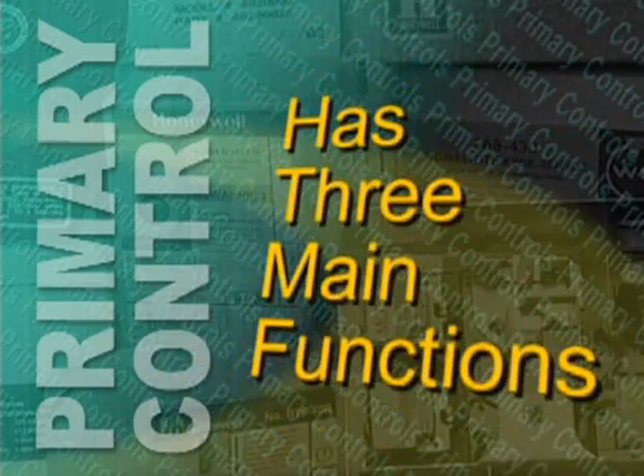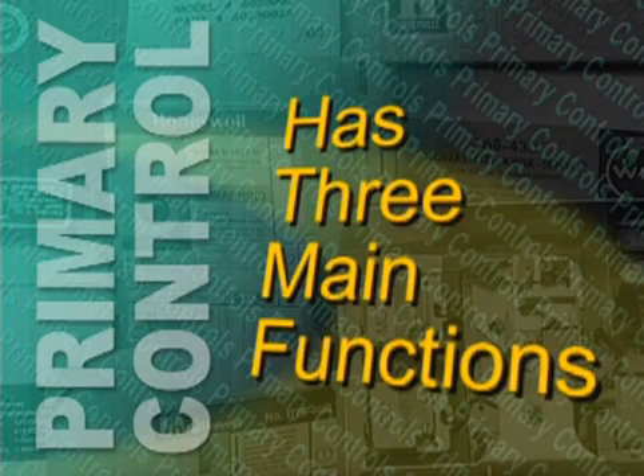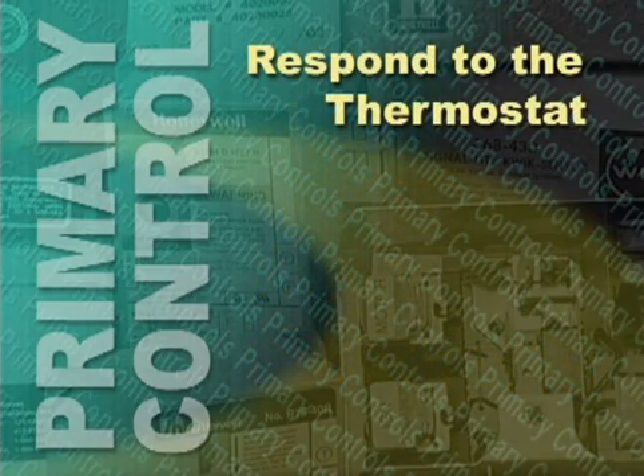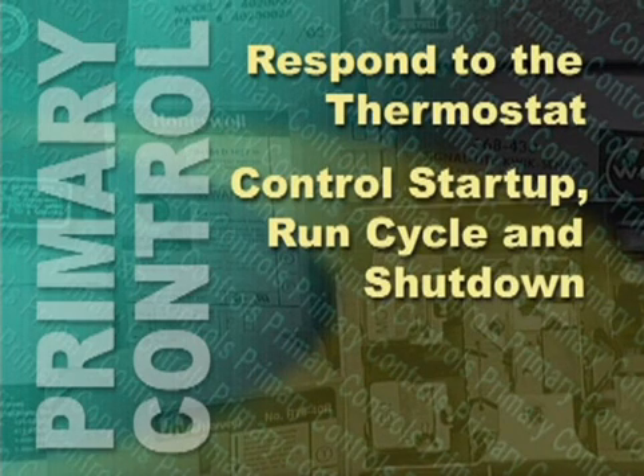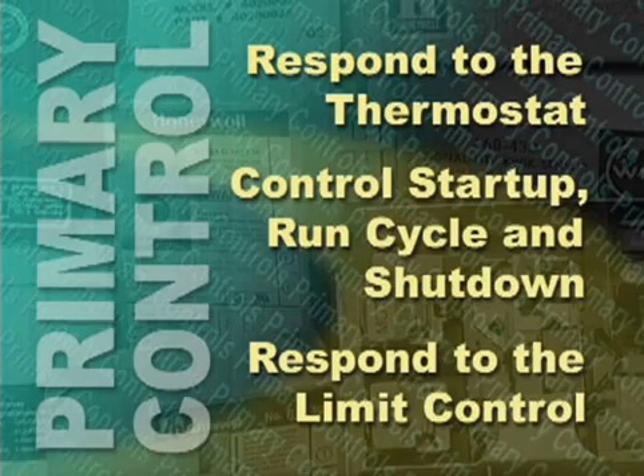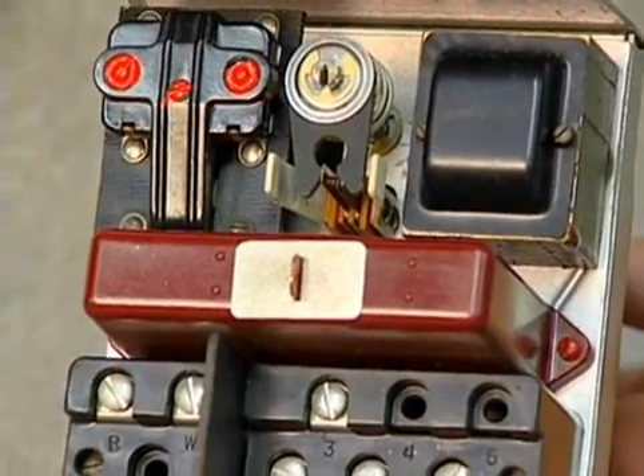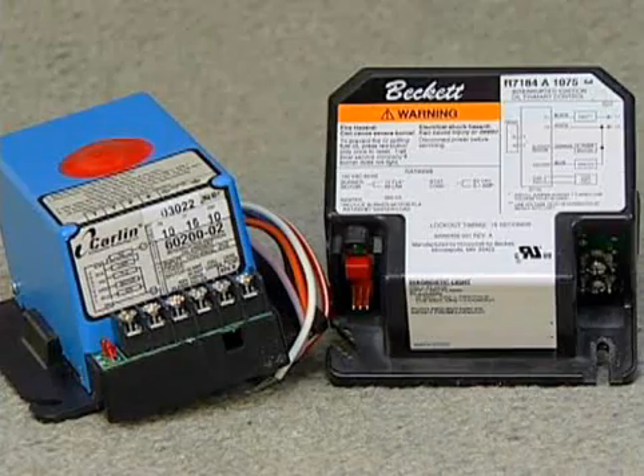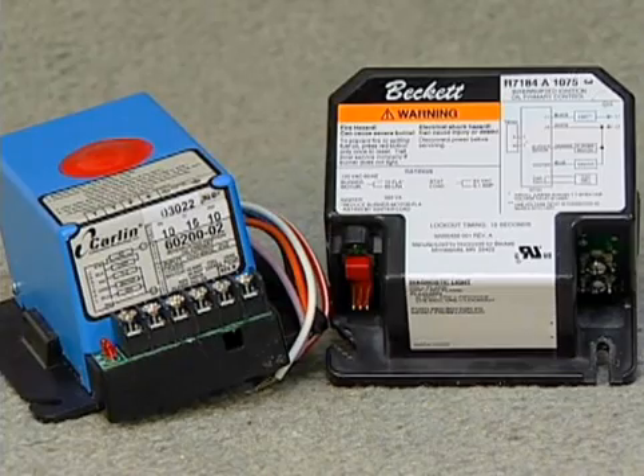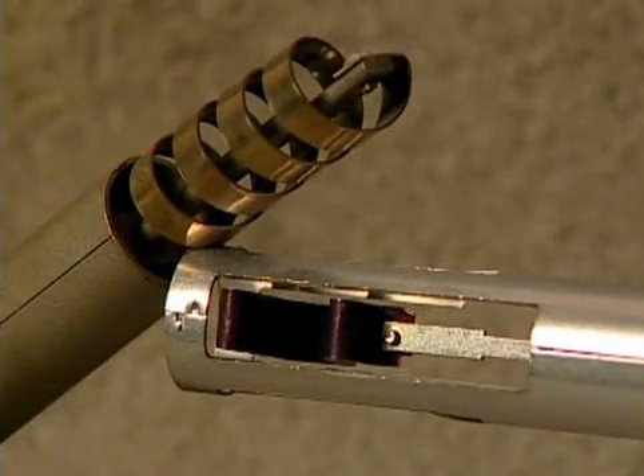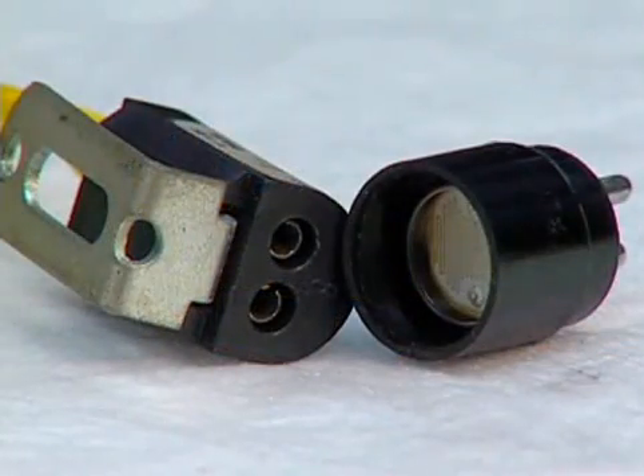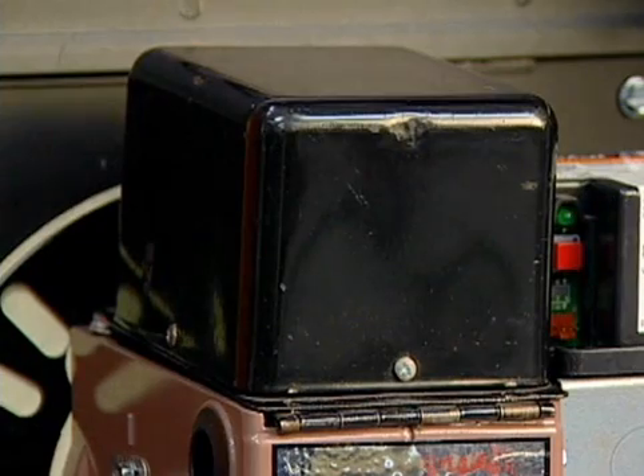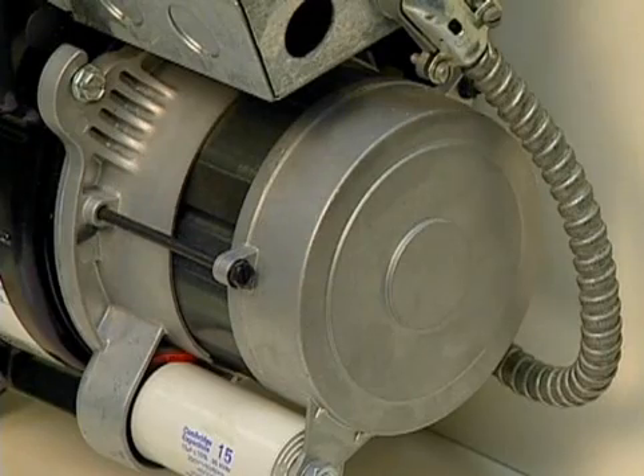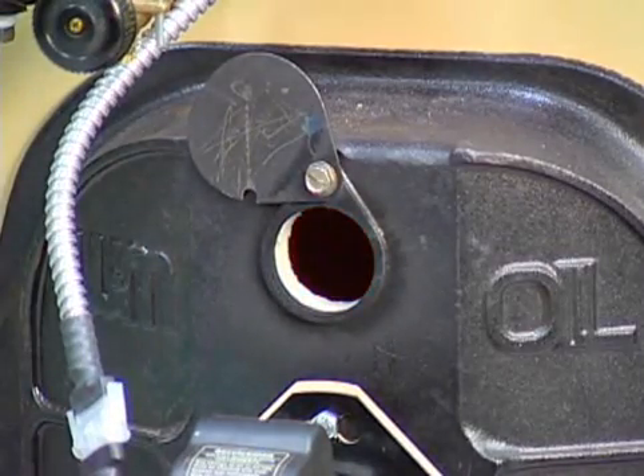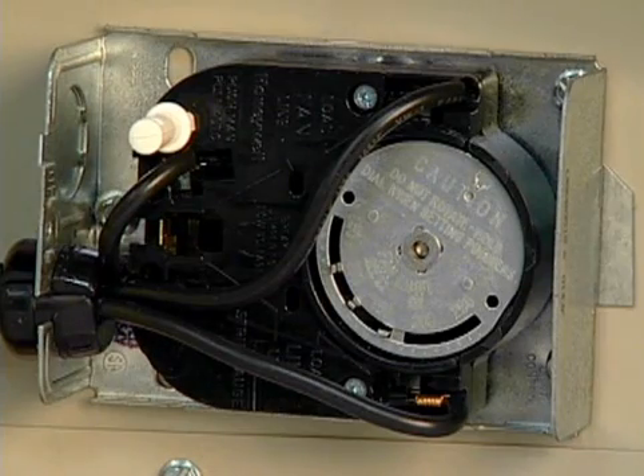The primary control, often referred to as the heart of the oil heat control system, has 3 main functions: to respond to the thermostat, to control the startup, run cycle, and shutdown of the oil burner, and to respond to the limit control if necessary. While primary controls have evolved from relatively simple stack switches to modern microprocessor-based devices, the basic principles of their operation have remained the same. The primary control accomplishes its mission by reacting to the presence or absence of flame through thermal or visual means, managing burner startup by checking for a flame before powering ignition transformers or igniters and energizing burner motors and oil valves, and supervising burner shutdown once the thermostat is satisfied or the limit control opens.